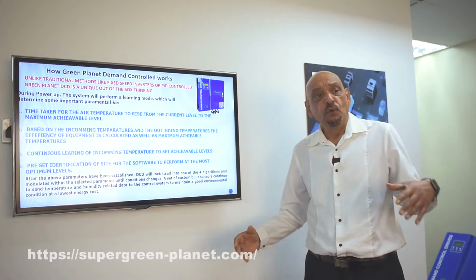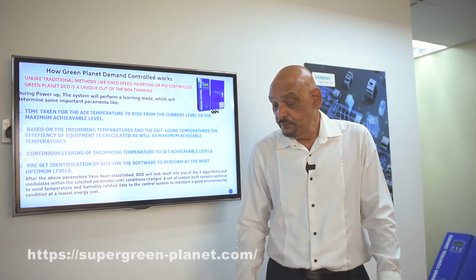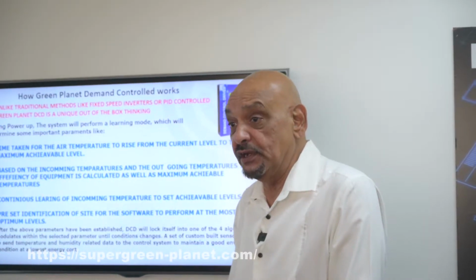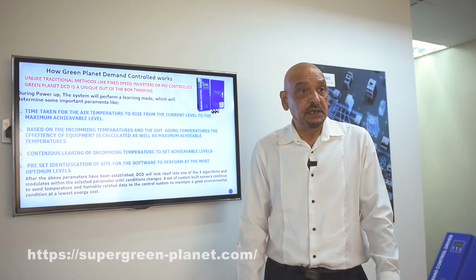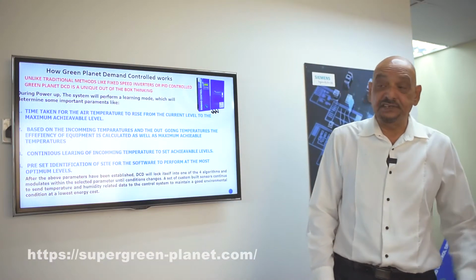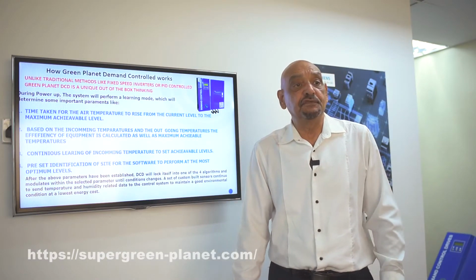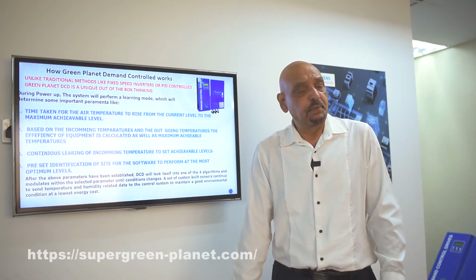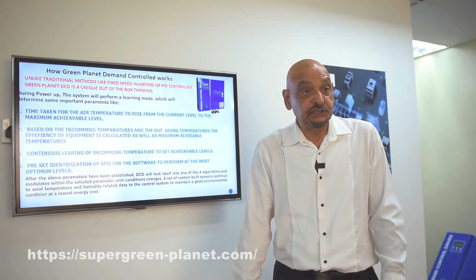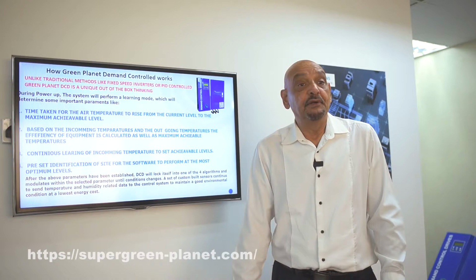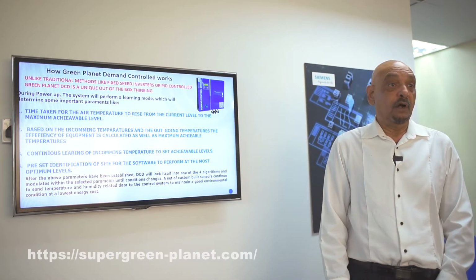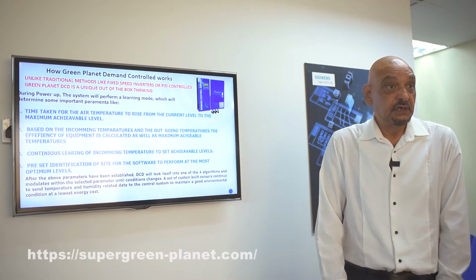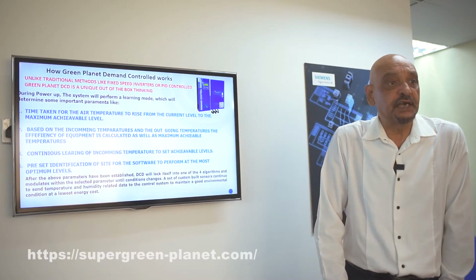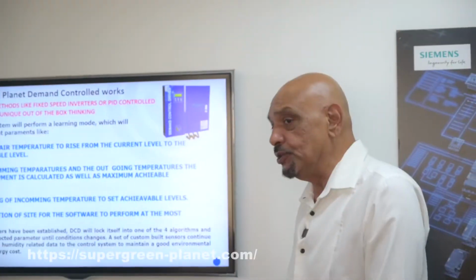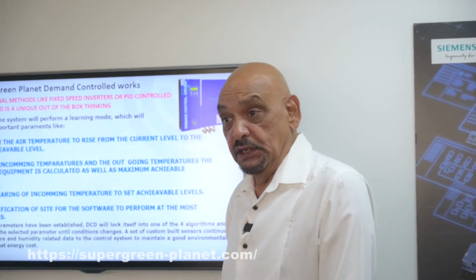Now, what happens here is that when a DCD, for example, is applied to an air handling unit, we have a sensor which is planted at the incoming duct, and a sensor which is planted on the outgoing duct. At the beginning of the day, let's say you get an instruction from your building management system, or if you don't have a BMS, you may just have a timer. When the instruction comes in, the system would start. At the beginning of the start process, the system will give you soft starting. Soft starting means that it gradually builds up the speed within your air handling unit.